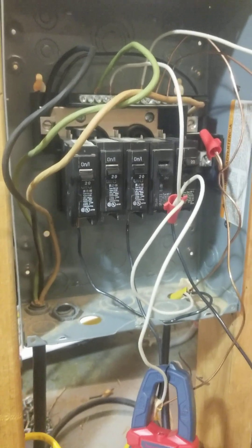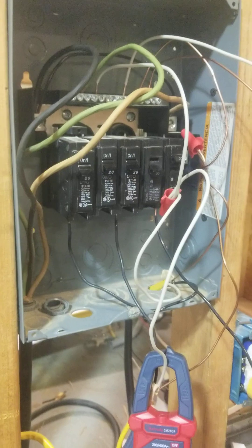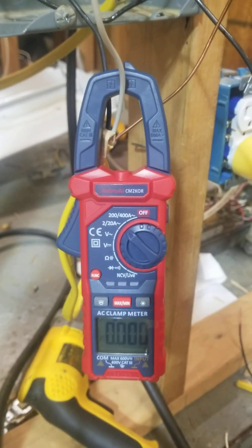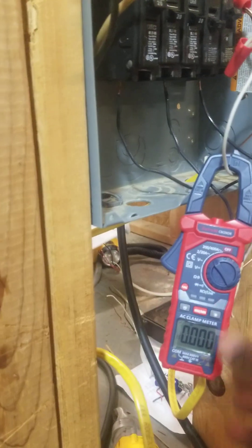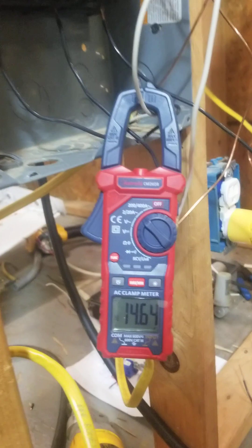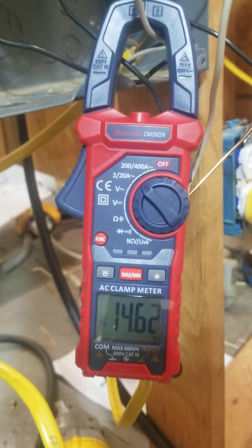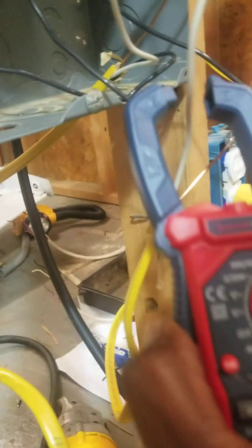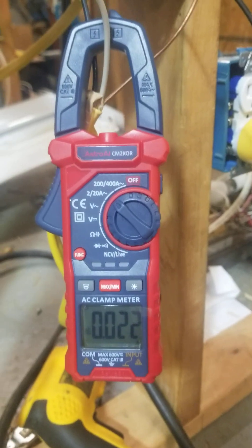It only takes 0.04 amps to start to do some damage and you can actually get killed at 0.06 amps. As you see, this particular circuit is off. Now let me show you how many amps this is drawing — I'm going to turn this breaker on for the heater. I'm already reading 14 and a half amps. Now I bring it over here and remember I had zero amps earlier — I'm already picking up 0.02 amps.